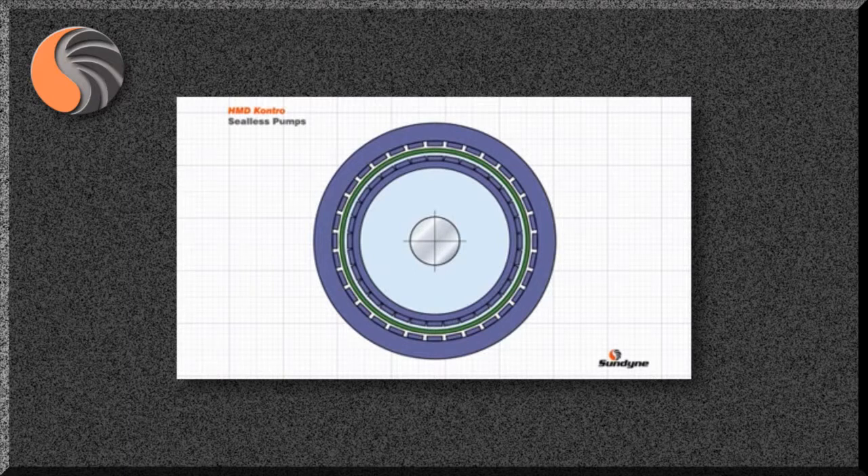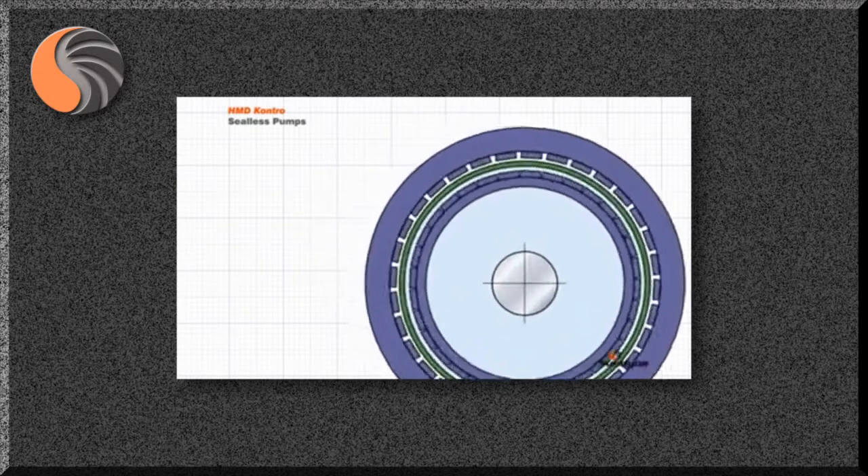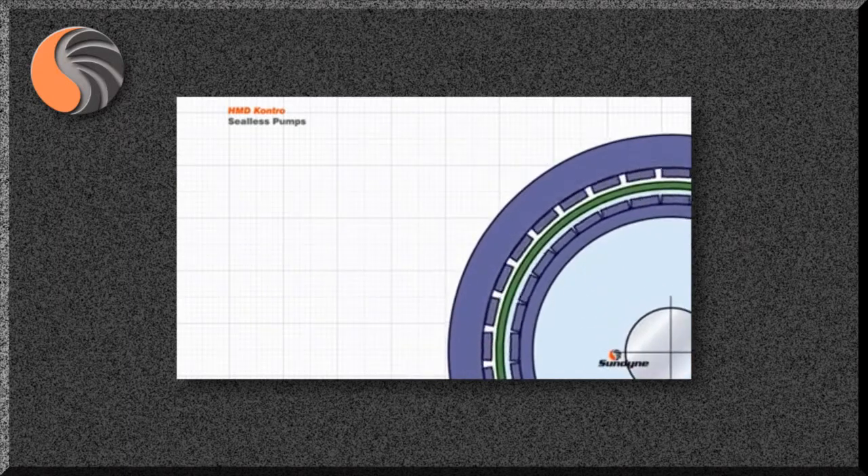To help understand how the magnetic coupling works, this animation views the coupling axially. The containment shell, shown in green, is positioned between the two attracting magnetic rings and will be subjected to the rotating magnetic circuits as the outer and inner magnetic rings rotate. For strength and temperature resistance, the containment shell is usually manufactured in a metallic material, which is electrically conductive. It is this property and the rotating magnetic circuits that causes eddy currents to be induced in the containment shell.